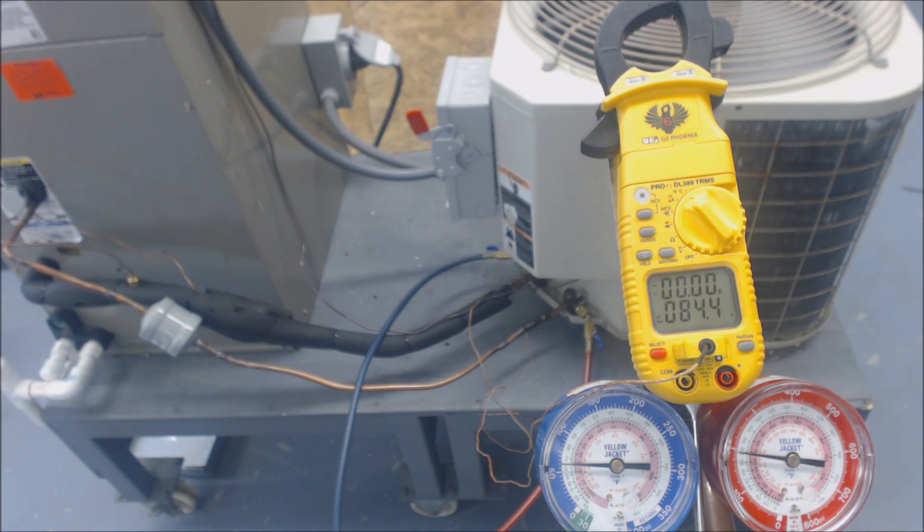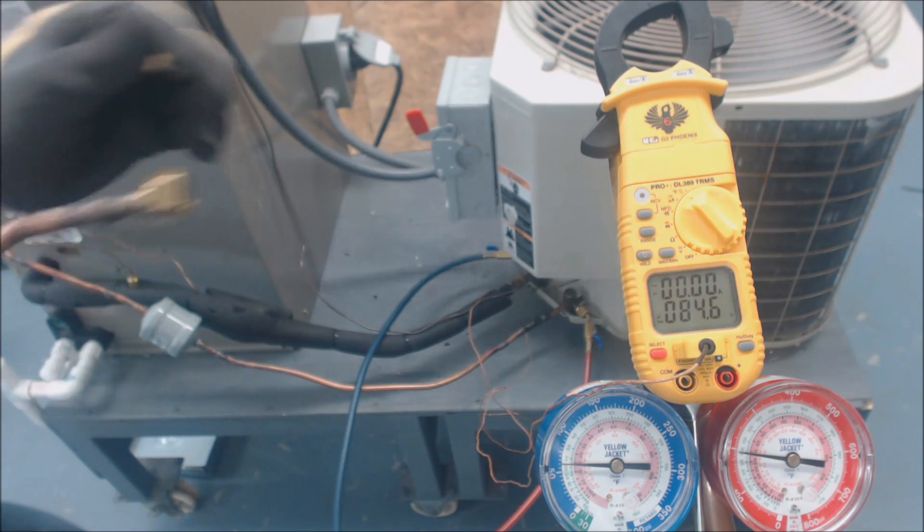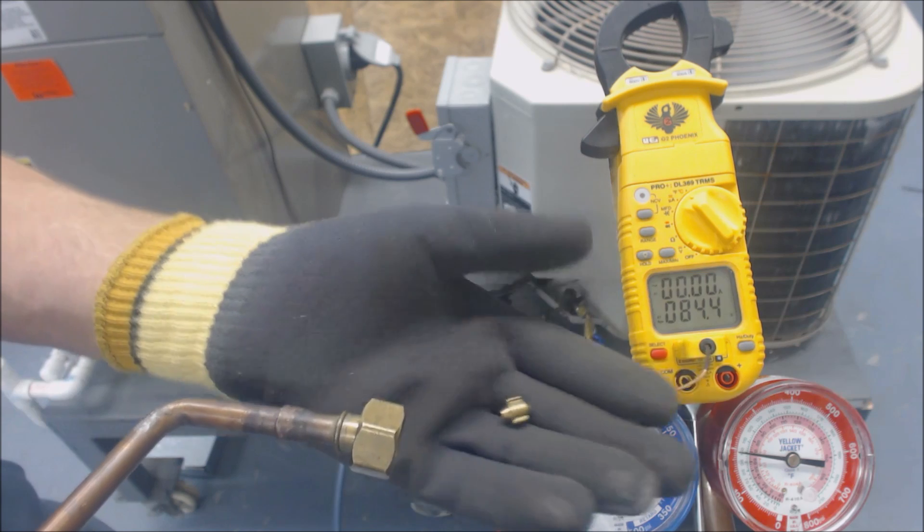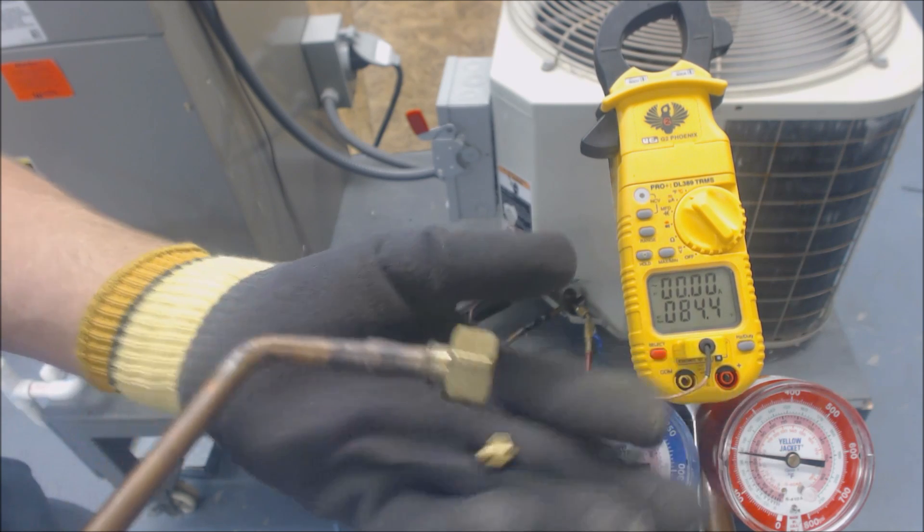Therefore you should use the subcooling charging procedure to figure out if this has the correct charge. You would not use superheat. Superheat would be used for pistons, orifices, and capillary tubes. That's the only time you would use a superheat charging process.